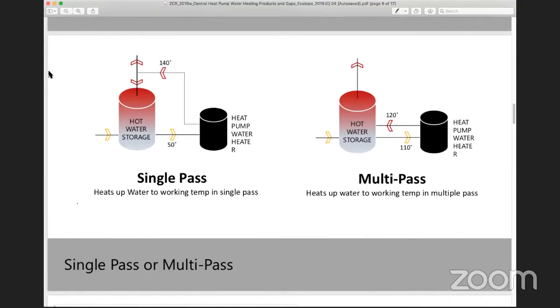One really important distinction in heat pump water heating: there are devices or heat pumps that are set up to heat water in a single pass, and there are devices that heat it in a multi-pass. The multi-pass is similar to a gas boiler indirect tank. A single pass actually has a device that throttles the flow so that you can get a really high lift. So incoming water at 50, out at 140.